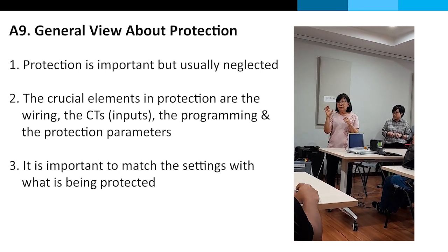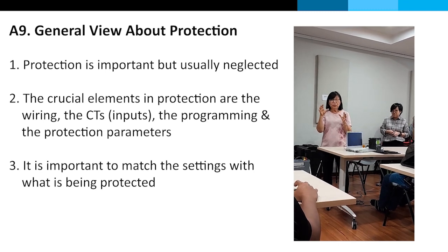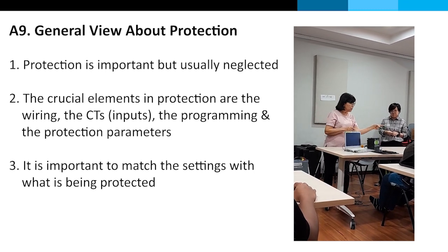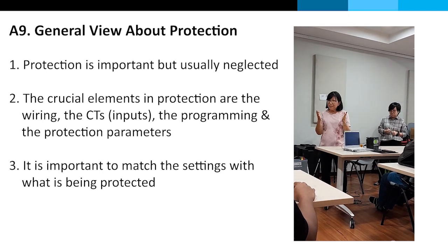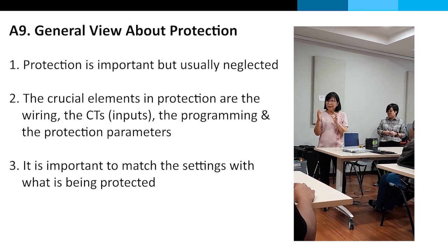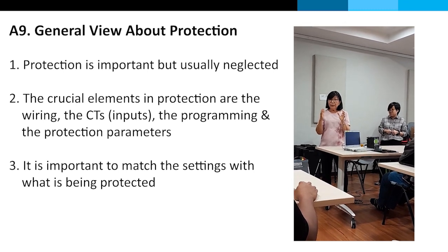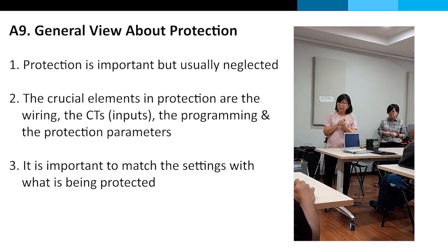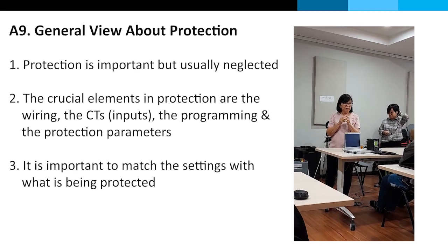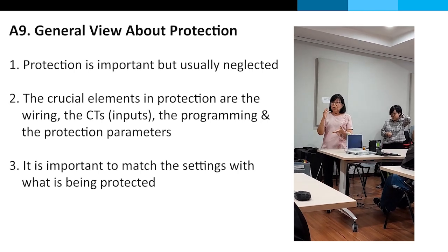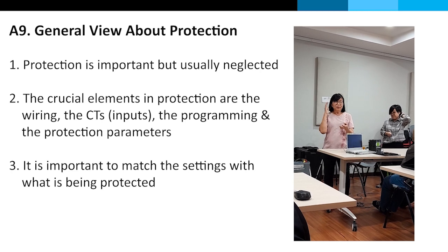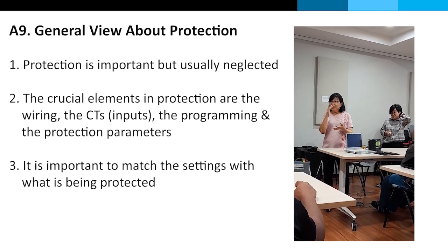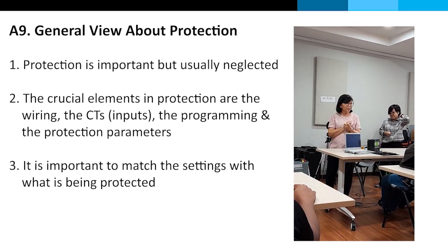But today we are not looking into protection settings because you have to match the motor. So how much can this kerusi tahan? We don't know, lebih kurang. So for this motor, how much dia boleh tahan, berapa lama, 6 times, how many starts per hour, we don't know. But the manufacturer knows and they will give you the data. So for Petronas, normally during commissioning, they akan bagi you a lot of data. So this data is not pening kepala, tapi very important for you to match dia punya setting lah.